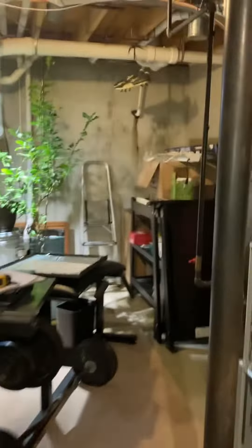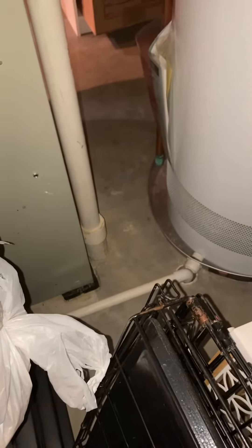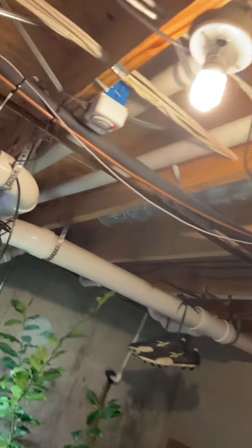It's set up for high efficiency — we've got two-inch piping making its way out. With the furnace, we've got good room to work with. As far as the drain's concerned, it's just tucked in behind. You can see the water heater's sharing that as well. It's in PVC at the moment. Somebody looks like they did a decent job on the venting to the outside.